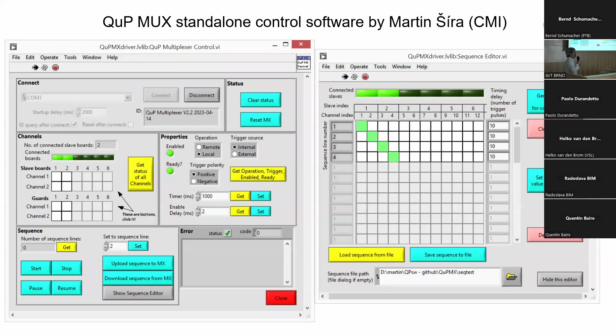And here is the important part, where you can program the sequence. As I said before, it's like a matrix. In the column, you have the channels: slave 1 channel 1, slave 1 channel 2, slave 2 channel 1 or channel 3, channel 4, and so on. And on the row, you program the states. When it's green, it means it's closed. And here is the number of periods and the number of triggers which this channel remains closed, so in this example, 10 trigger signals. Then this sequence can be stored in a file, and you can load it with the software, and then you can upload to the multiplexer, or you can download from the multiplexer.